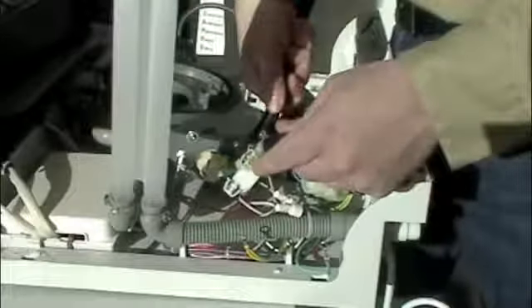The next part I'm going to talk about here is our actual flow meter. Now I've disconnected the wiring to it. As you can see, there's a plug there. However, this part is what actually does all the measuring on the unit, and it will tell us and will give us an error code if the water pressure is not right. So those are some basic parts, how they work and how they relate to water pressure problems.